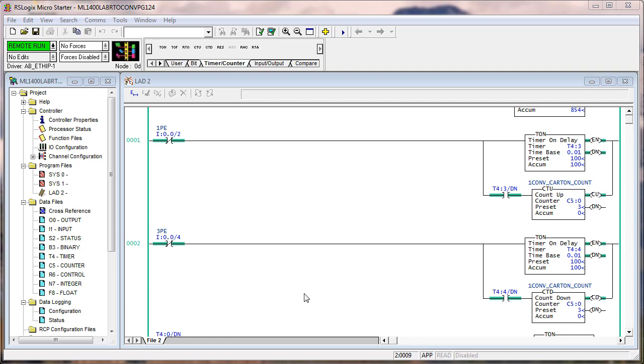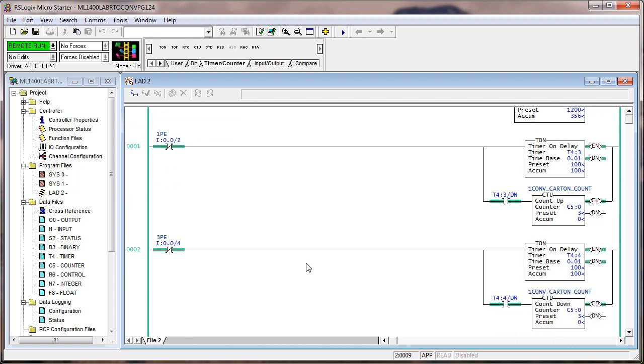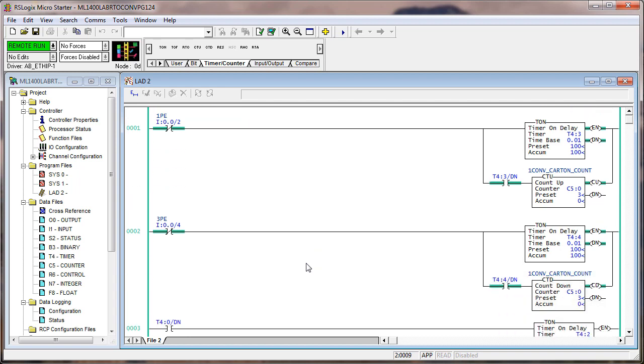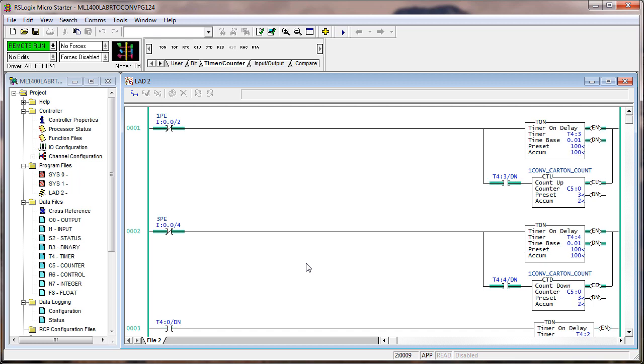Now we go back to 1 PE and 3 PE. And I'm going to turn on 1 PE. Make sure our conveyor is still running. Yes, it is. I'm going to turn on 1 PE, which is input 2. And it stays on as long as the carton is blocking the optical path. But notice it doesn't count. C5 0 still 0. When it clears 1 PE, a one second timer starts and one second later the DN bit from the timer does the false to true transition for the count up addressing C5 0. If another one comes in, it's blocking. Remember it doesn't get counted when it blocks the photo, only when it clears. And one second after it clears. Do another one passing in front of 1 PE, clears 1 PE. One second later it counts up.